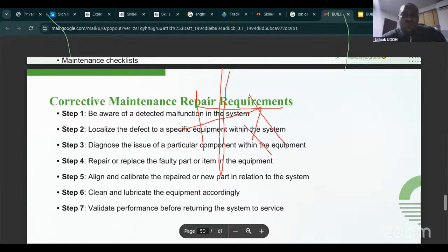Then we do proper cleanup, clean and lubricate the equipment accordingly. Some call this housekeeping, tidying the surrounding area to make sure the job is completed. Then validate performance before returning the system to service, checking that the performance of that unit is fine, that the hissing noise or sound is gone, and everything is back to normal.